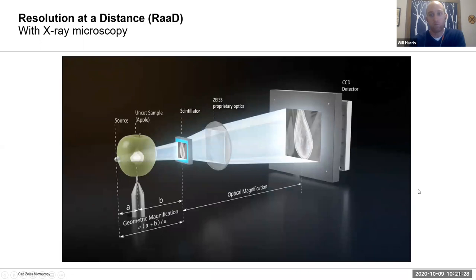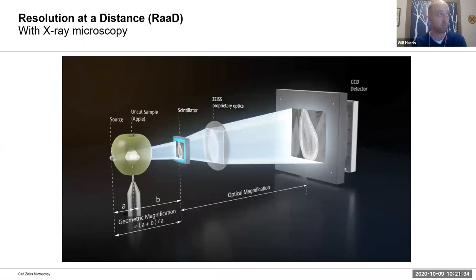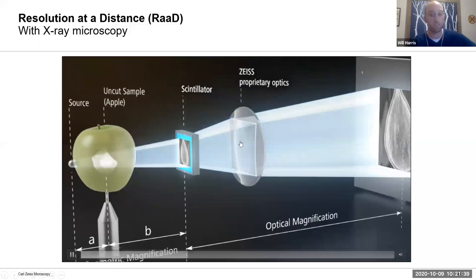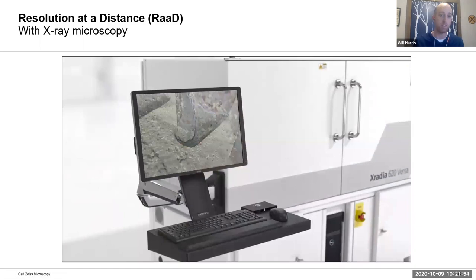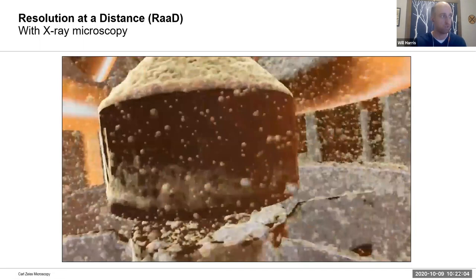About ten or fifteen years ago Xradia came along and did something different: they changed the detector design to incorporate some optical elements so that they could further magnify the image before ultimately collecting the data. You can switch optics and change the level of magnification at the detector level, which is pretty unique in the lab-based space — use that to zoom in on the interior of objects and get super high-resolution compelling data inside something without cutting it open.